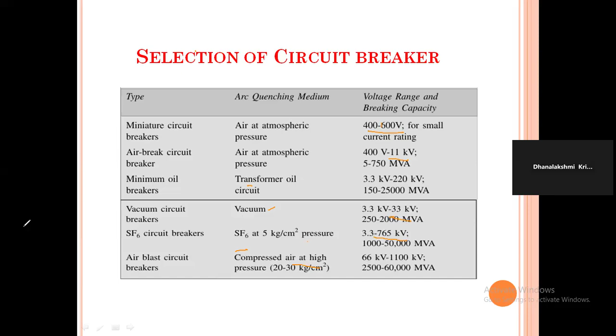So which circuit breaker is preferred for which voltage? Below 1 kV, definitely the air break circuit breaker is used. At 3.3 kV, different ranges are available: vacuum circuit breaker, SF6 circuit breaker, minimum oil circuit breaker. Up to 33 kV, the vacuum circuit breaker is preferred. At 132 kV to 220 kV, SF6, air blast and minimum oil. Here the minimum oil circuit breaker is also used, but SF6 is more preferred, and from 400 kV to 760 kV only the SF6 circuit breaker is preferred.